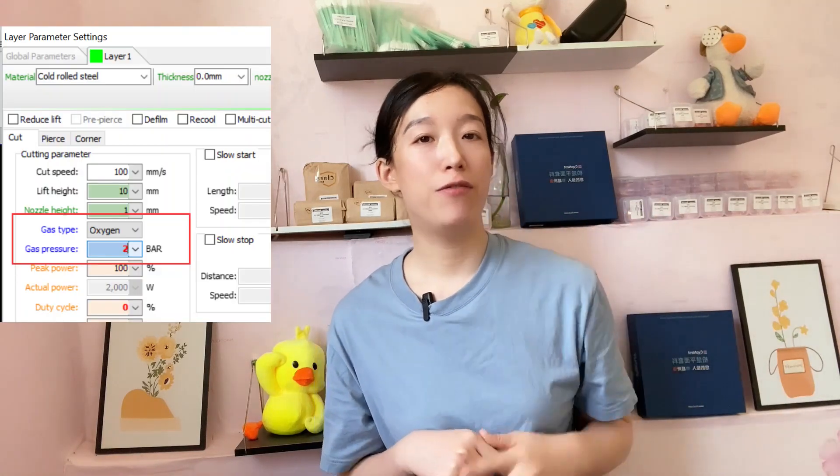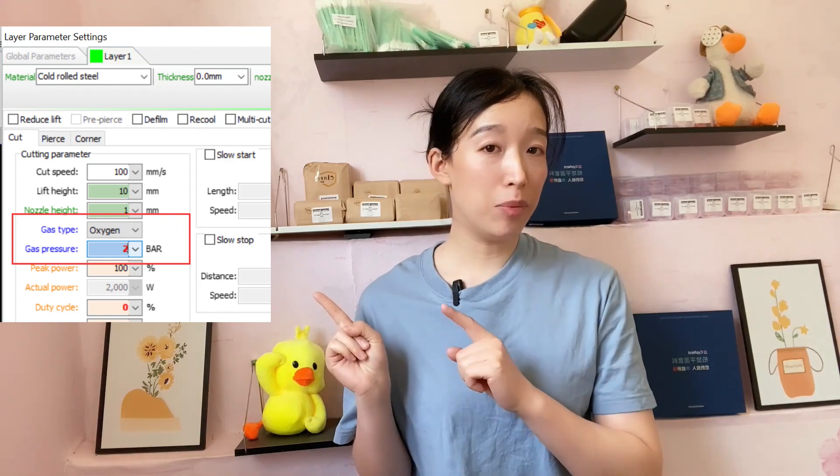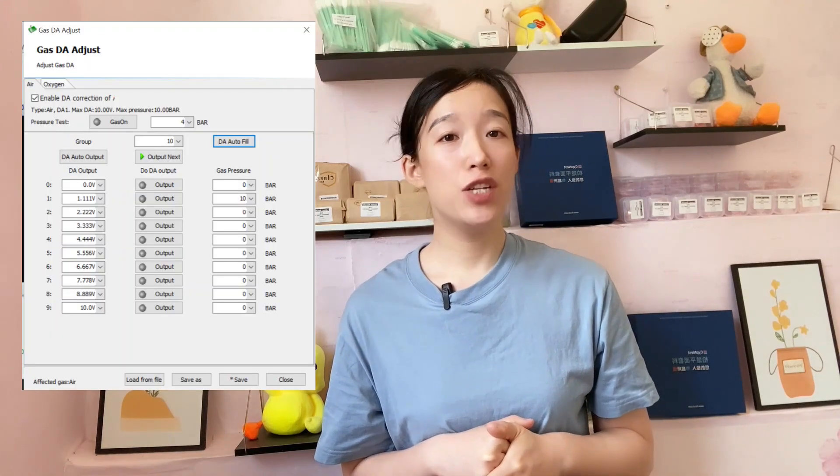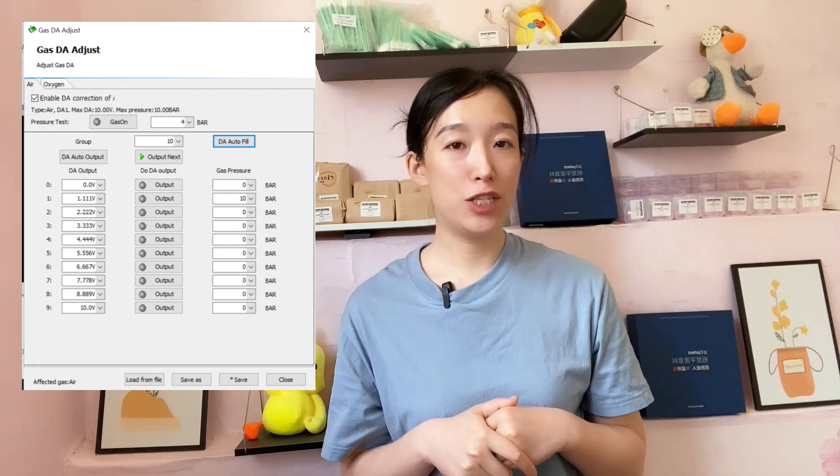There can be no gaps. Let me take an example to help you understand gas DA correction. Let's say I need 2 bar for cutting and I input the number 2 in the layer parameters, but it turns out there is only 1 bar shown at the proportional valve. That's the problem — the actual gas pressure doesn't match what we set. What should we do? First, check whether the wire connecting the proportional valve to the board is causing interference, as that may cause abnormal output. Second, if interference is ruled out, we need to perform gas DA correction following the steps described above.